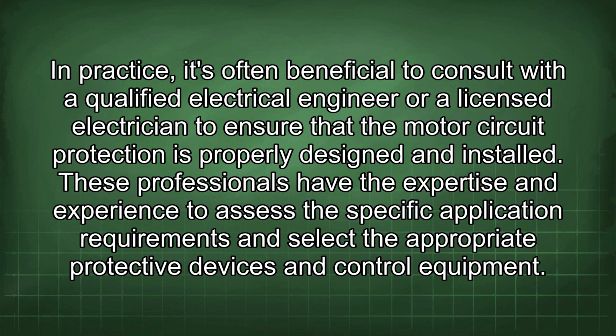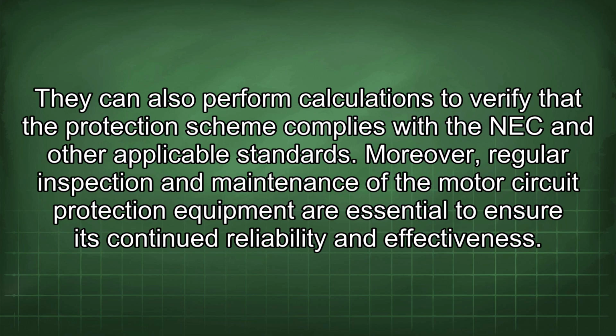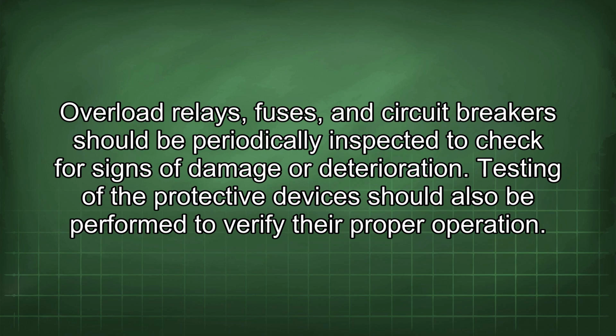These professionals have the expertise and experience to assess the specific application requirements and select the appropriate protective devices and control equipment. They can also perform calculations to verify that the protection scheme complies with the NEC and other applicable standards. Moreover, regular inspection and maintenance of the motor circuit protection equipment are essential to ensure its continued reliability and effectiveness. Overload relays, fuses, and circuit breakers should be periodically inspected to check for signs of damage or deterioration. Testing of the protective devices should also be performed to verify their proper operation.